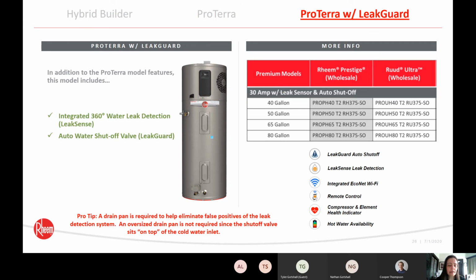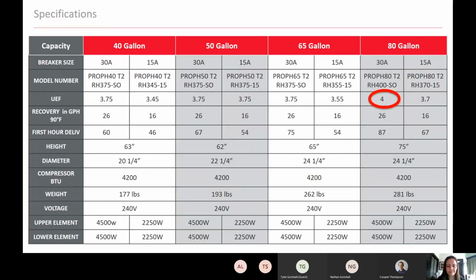Fantastic product. Quick pro tip for this model: we ask that a drain pan be installed to eliminate false positives. Right down here is a red wick that's absorbent, so if it were sitting on a basement or garage floor and there was an accidental spill, or even condensation from humidity, that could set off a false positive. So we ask that it be installed with a drain pan. Most of the time that's going to be to code anyway, but for those doing their own install where it's not to code, or in an area where it doesn't matter, please still install with the drain pan.